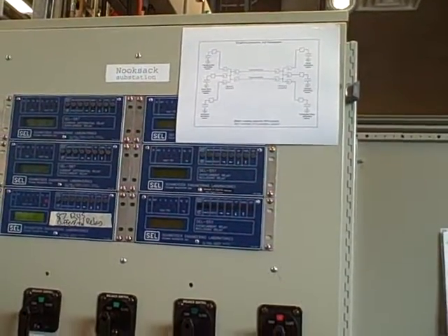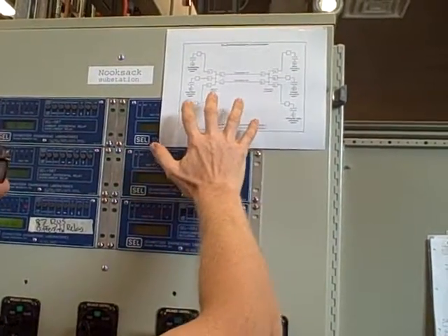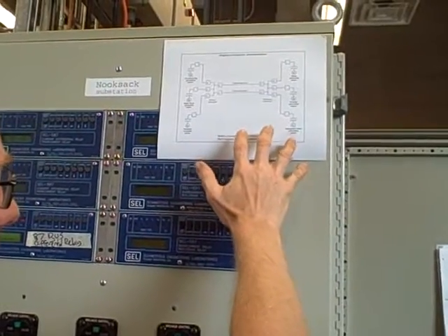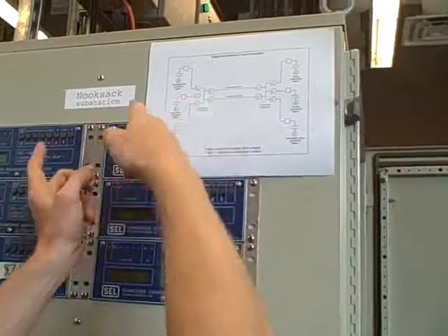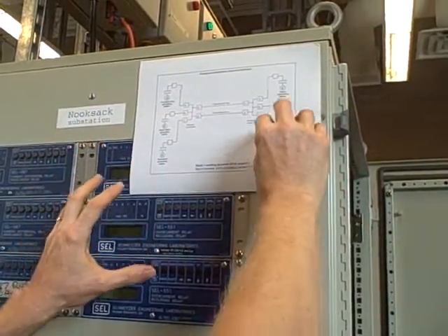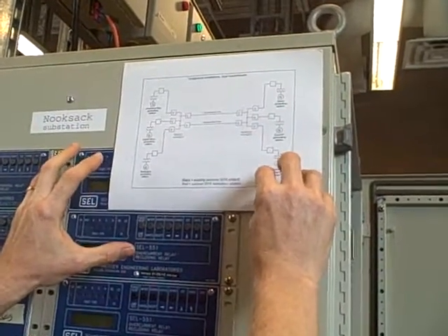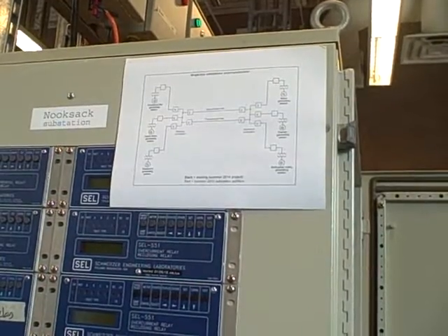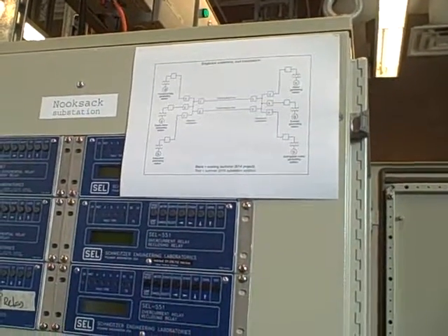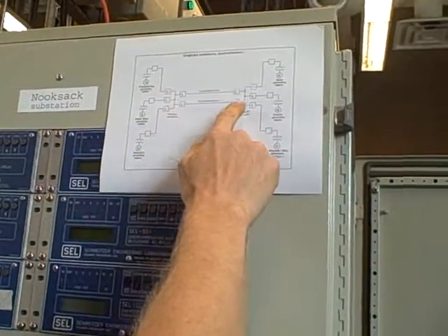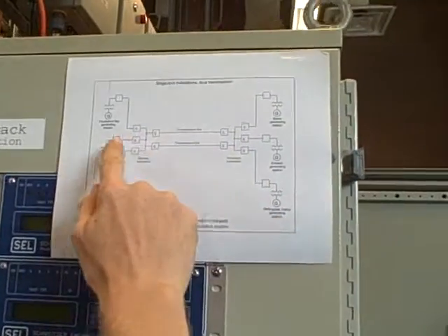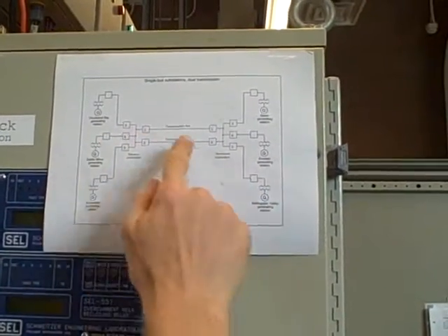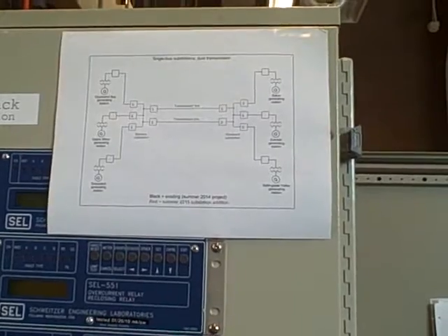But we're doing this because right now, it's an easy way for me to put an adjustable load on my system. I can shift the flow of power back and forth just by changing the prime mover speed of my generator, making the generator try to push or pull the system as much as it can. So what I've done is adjust so we've got a load of about a half an amp of current per phase through the system. And so far everything's running that way, everything's happy.